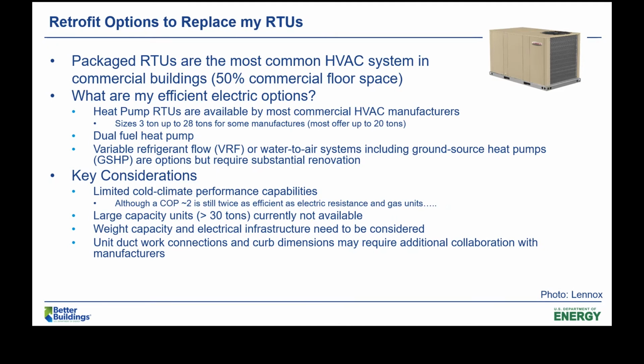And we actually get that question a lot: what about the performance? I hear that heat pumps don't perform well. One thing to keep in mind is that yes, their coefficient of performance, their COP, might go down. It might be 2 or 1.5 at lower ambient conditions, but that is still 50% or more efficient than just electric resistance. So when we're really looking at high performance beneficial electrification of HVAC, we want to choose the most energy efficient option, and heat pumps are more efficient than electric resistance, oftentimes tremendously more, with a coefficient of performance of 3 or more throughout the year.